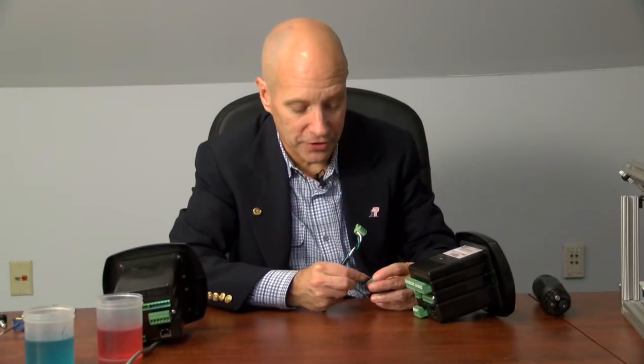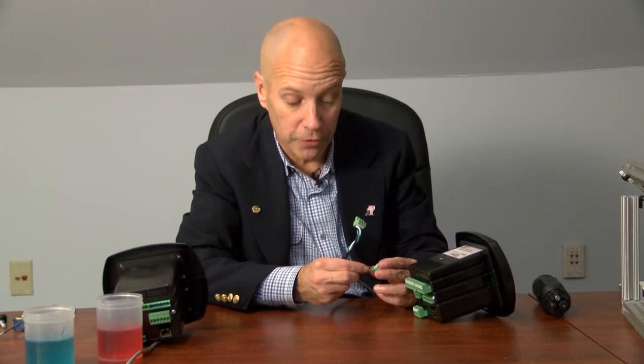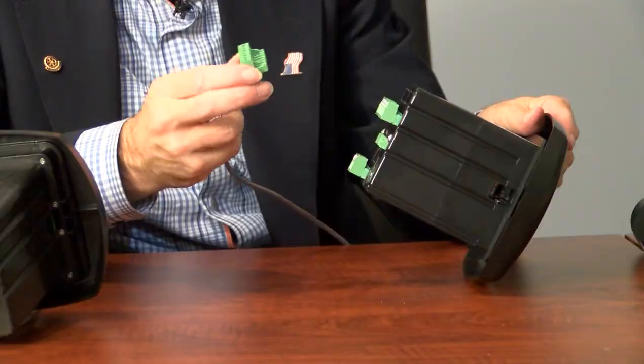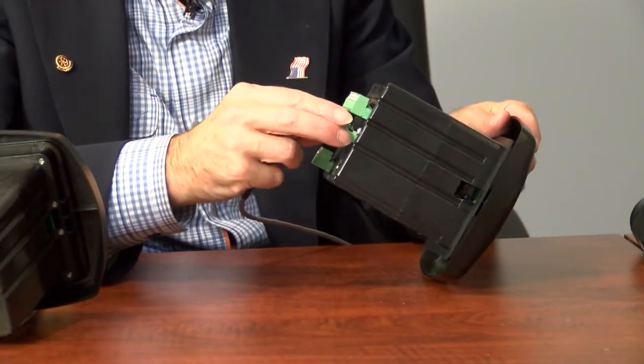Some 4-20 milliamp sensors require more power than that which is available from the loop. These sensors have a 3rd wire for power, so that they are typically called 3-wire sensors. The connection of your sensor depends on whether you have a loop-powered sensor or a 3-wire sensor. Okay, let's connect everything together. I've already wired up the red wire to the 24 volt terminal and the black wire to the analog number 1 in. All I have to do now is insert the connector into the back of the unit.